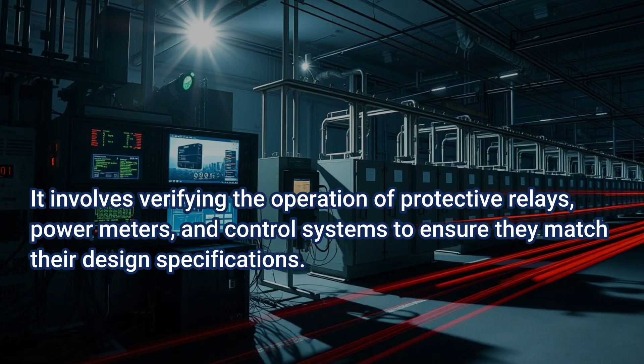This includes measuring things like voltage, current, power, and time delays in protective relays during faults, while also ensuring proper coordination between primary and backup devices. For more accurate measurements, high-frequency sampling and synchronization with universal time are required, especially in systems with distributed energy resources like solar or wind power.